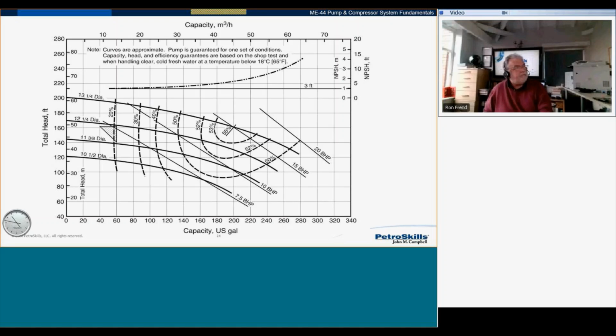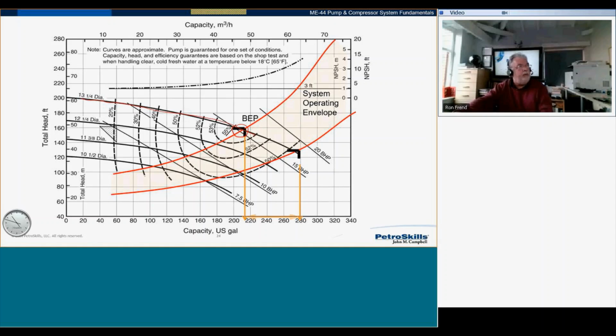Implications of this. Well, here's one. Let's put our system curve on there. We're going to be working on this pump, using the large impeller. So that is my operating point, which is pretty close to best efficiency point, BEP. That's nice. But when I do my sensitivity analysis, there's my system operating envelope. That's my new operating point. I'm right at the end of the curve. The chances are, if I'm operating way down here at the end of the pump curve, my pump is going to be cavitating. You're going to have cavitation problems.